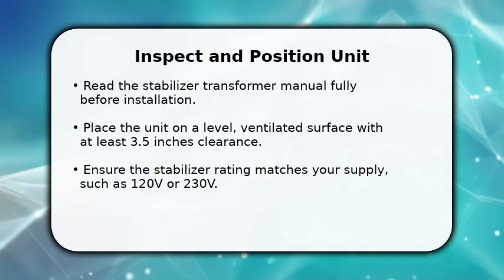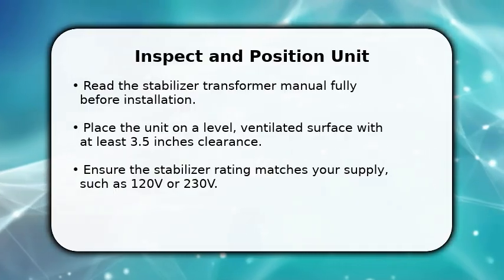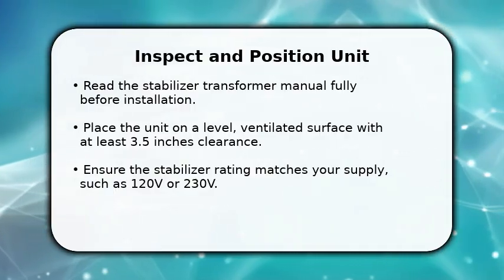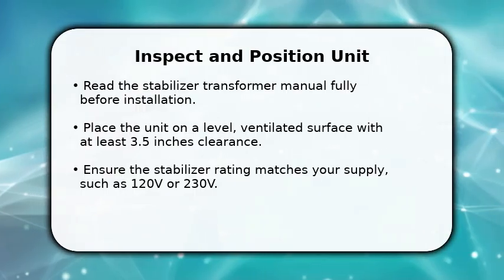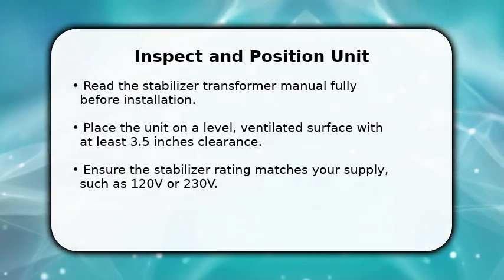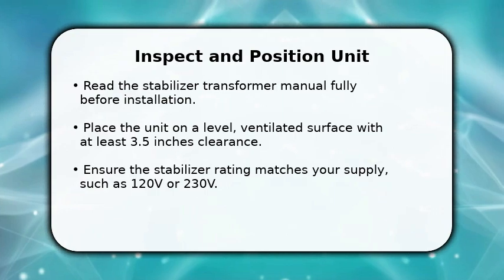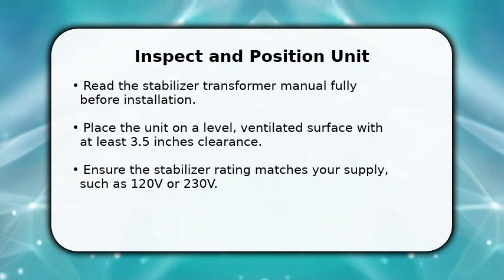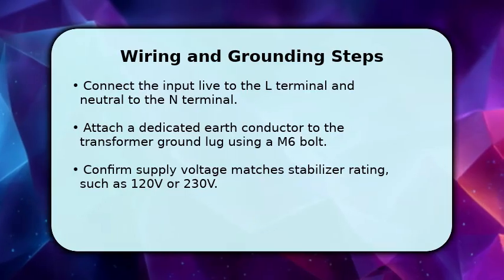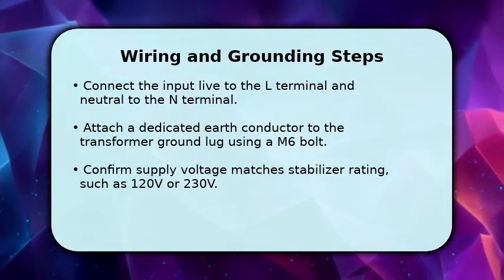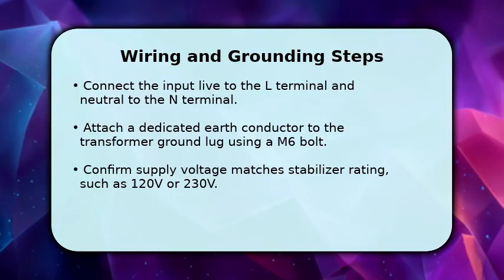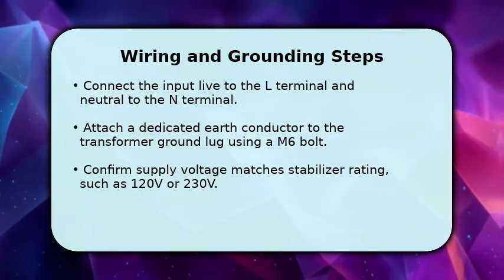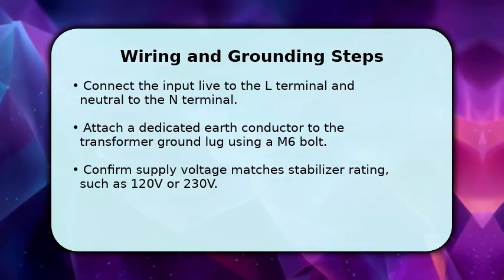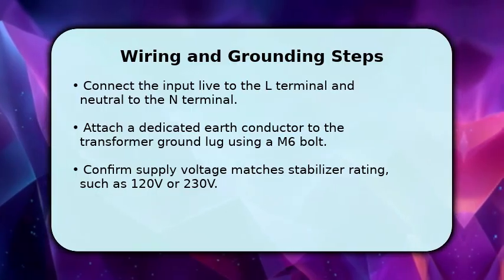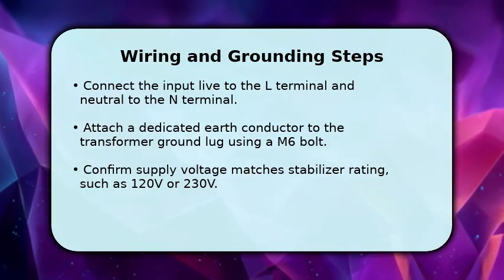Ensure the stabilizer rating matches your supply, such as 120V or 230V, and confirm the kVA rating meets your load needs. Turn off power at the main breaker before proceeding with any wiring or mounting steps. Connect the input live to the L terminal and neutral to the N terminal. Use appropriately sized conductors. For loads under 15A, use 14 AWG, and for higher loads use 10 AWG or larger.